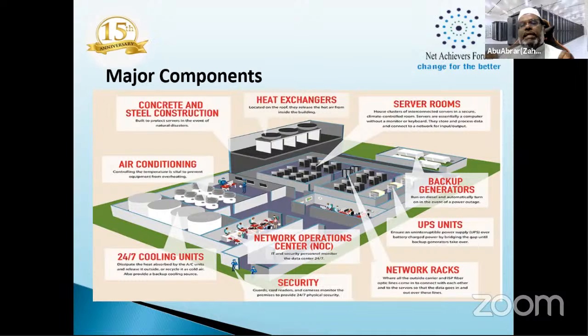Under the raised floor, cold air is passed through. Wherever we need it, we perforate a tile and get air from the perforated tile. Some smart perforated tiles exist too, with a fan and sensors. You can set the sensor so a particular rack gets, say, 22 degrees Celsius of cooling, and the fan will pull air from below and push it to those racks. These are called smart tiles. Normally a perforated tile has grills or holes. In the modern world, there are aluminum holes with a galvanized metal base. There are several types of tiles.